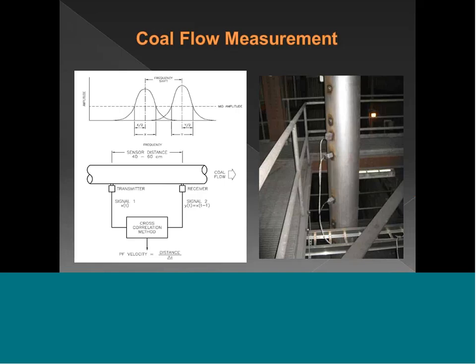The pulverized coal flow technology that we use is not a single technology, it's two technologies. We use microwave to measure the mass of the coal, and we use electrostatic cross-correlation to measure the speed of the coal in the pipe. Typically we use two sensors as shown here on the bottom left, a transmitter and a receiver. On the right they show up as this is the transmitter and this is the receiver, the up and downstream sensor. In the picture on the right I've chosen to show a third sensor, and I'll explain that.